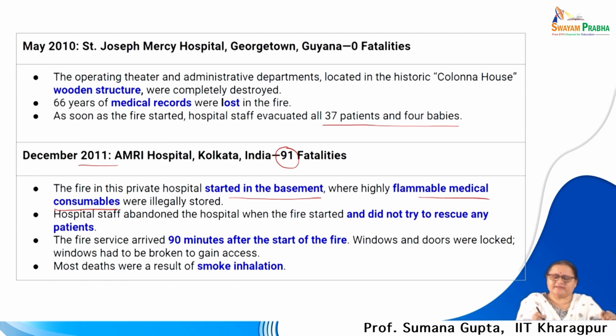These flammable medical consumables somehow caught fire, and the entire smoke that was built up was carried through the ventilation chutes and air-conditioned routes, and people were smoke-choked. No rescue operation was done promptly because it happened in the middle of the night when attendants were not alert, and it took around 90 minutes after the start of the fire for the fire service to arrive. So the whole response was a failure to some extent, and the deaths were due to smoke inhalation. This is how the fire moved vertically through the duct to different floors, leading to such a large number of fatalities.